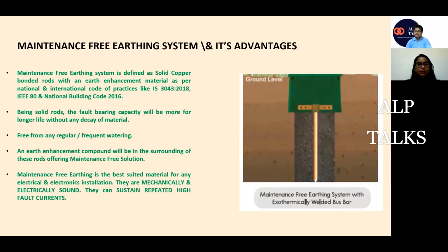So the advantages of using maintenance-free earthing are, first of all, that my earthing pit size has decreased, as we are talking about space constraints. With solid rods, the earth pit size has decreased. We do not require regular watering or frequent maintenance of the system. Once it is installed, it's installed. I just need to check properly that the earth resistance is maintained, which I can do once a year as regular maintenance. But the pit does not require any regular maintenance.